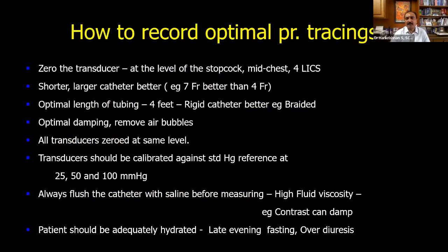So how to record optimal pressure tracings? Zeroing the transducer, I said, at the level of the stopcock, that is the three-way, mid-chest, fourth intercostal space, that is the phlebostatic axis. A shorter, larger catheter is better. For example, a 7 French will be better than a 4 French catheter, so that the waves will be transmitted accurately. Optimal length of the tubing will be 4 feet. A rigid catheter will be better. For example, a metal braided catheter will give better pressures.